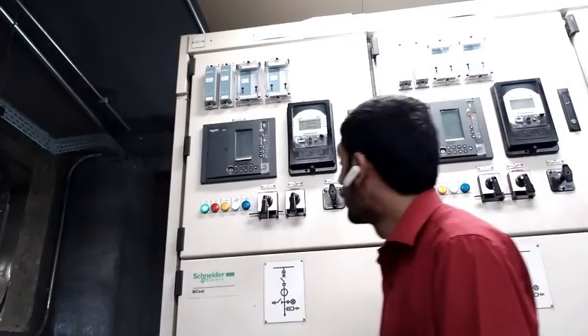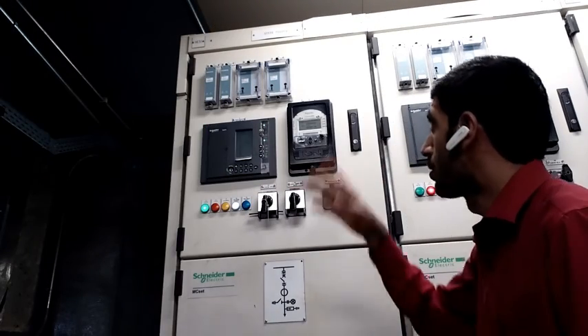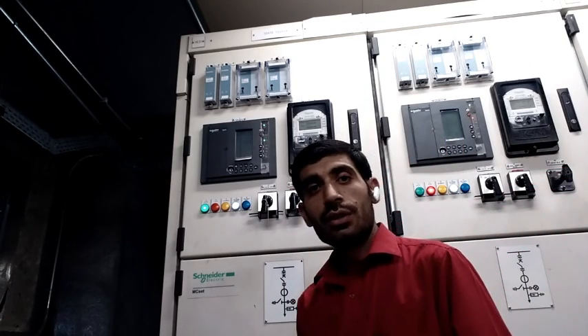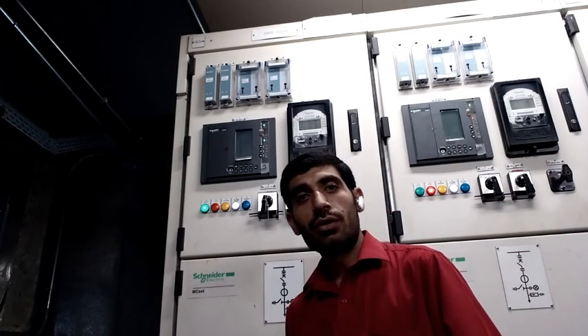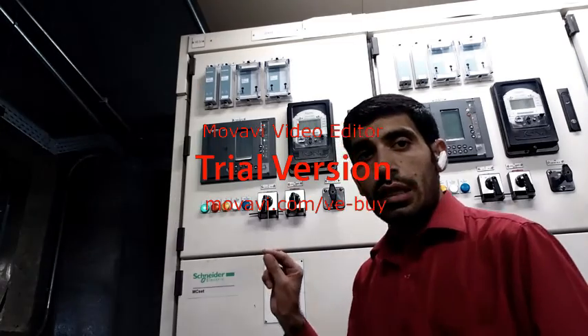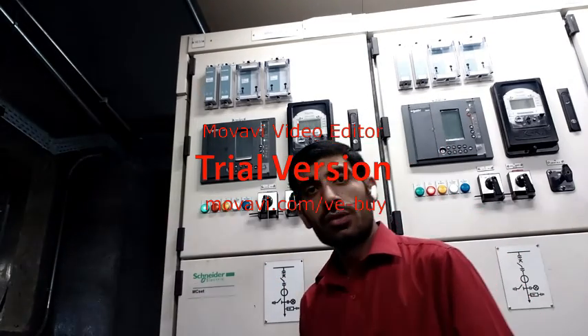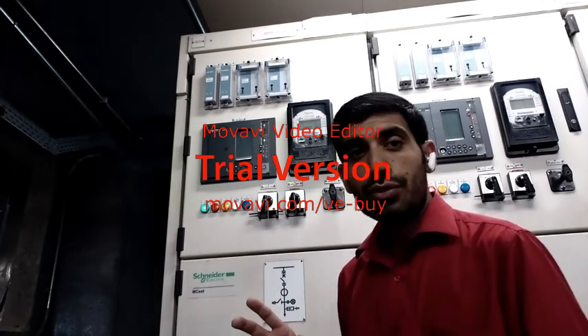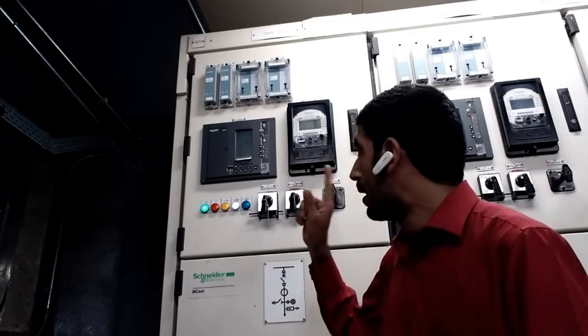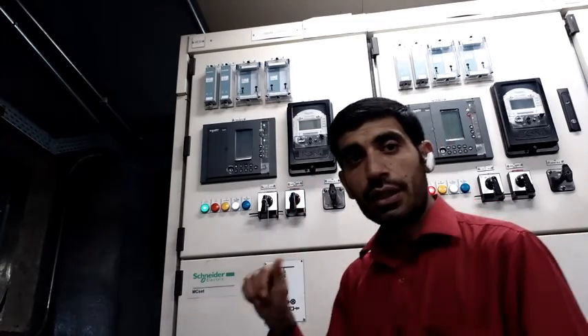And one more thing, we test all these things. How do we test all these things? They will actually test through Freja. We inject 125 volts on the coil of this relay and check the timing through binary contacts, how much timing for tripping timing of this relay. And we also test the pickup of this relay, how much pickup voltage, through Freja.